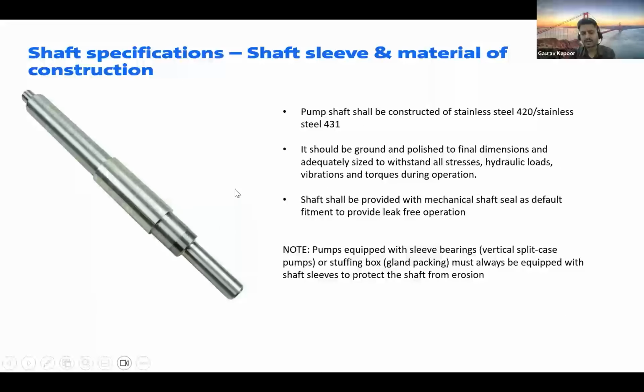So that's why, a few years before, new hydraulic designs came up where you do not need a shaft sleeve, because we have updated the shaft material from carbon steel to SS420 or SS431, which are highly resistant to corrosion. As a result you have fewer failure points in your pump, which again gives you a very long and healthy life for your operations and maintenance.